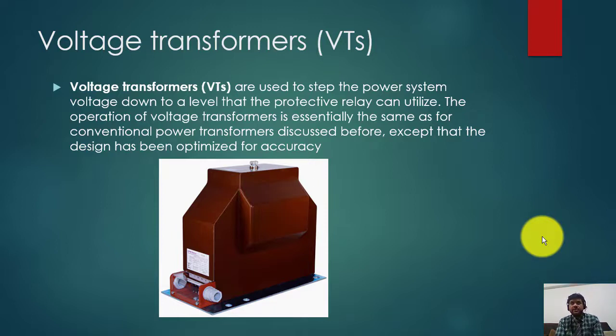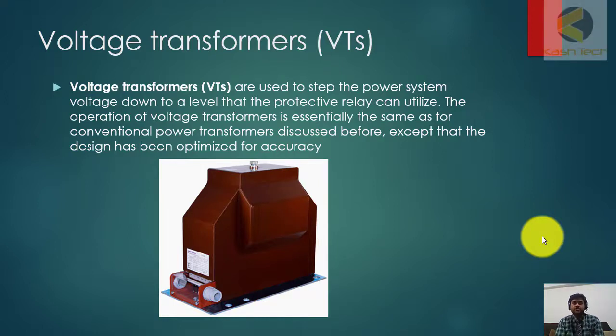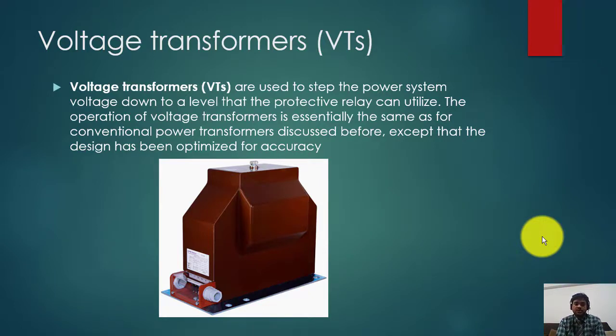If the relay reads 50% of the voltage — for example, the VT ratio is 132 kV to 100 volts — and 50 volts is coming to the relay, the programming we do in the numerical relay will show it as half of 132 kV. In this way the system works, and low voltages are very easy to handle at the secondary side.